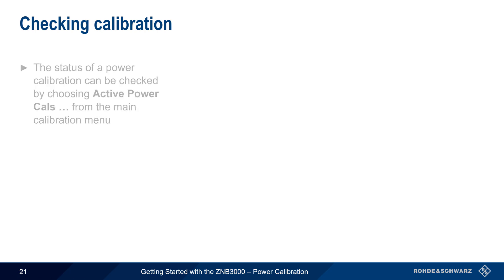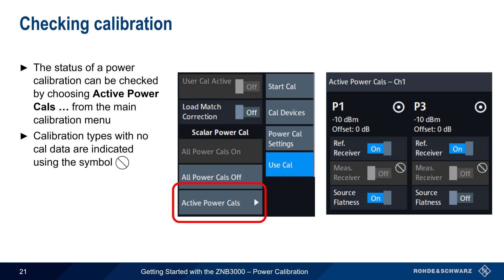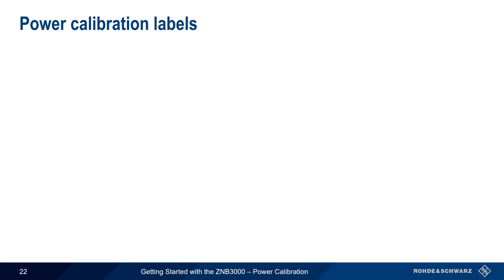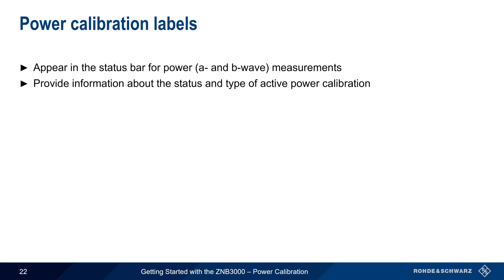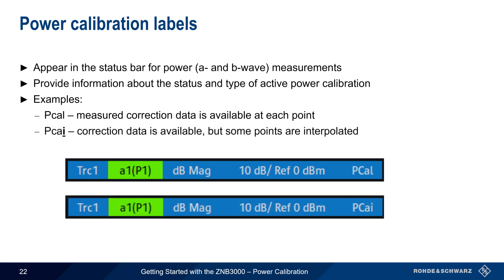Once power calibration is complete, the status can be checked by going to the Calibration menu and selecting Active Power Cals. Calibration types with no calibration data are indicated using a symbol, and an active power calibration can be individually activated or deactivated via this dialog. Power calibration labels appear in the status bar for any power or wave type measurements. For example, the label PCAL appears when measured correction data is present at each sweep point, while PCAI appears when interpolation is being performed. Please see the ZNB3000 documentation for a complete list of label types and meanings.